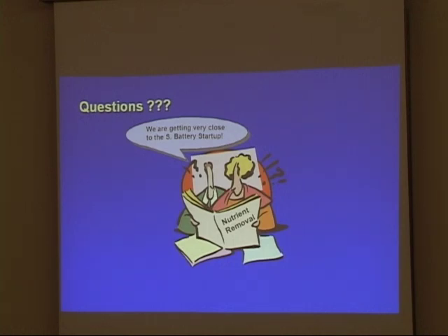So, that's it in a nutshell. Any questions, comments? I disagree with one of the statements on the hydraulic wasting. That's the box that says if the SRT increases to over 10 days, the pump wasting would need to be employed, which means they're coming off the RAS line because the pumps wouldn't have enough capacity. I think that's just the opposite. If you increase your SRT, you need to waste less volume, and based on that, you have more capacity with your pumps. So I disagree with that statement, but I respect your ability to make that statement.